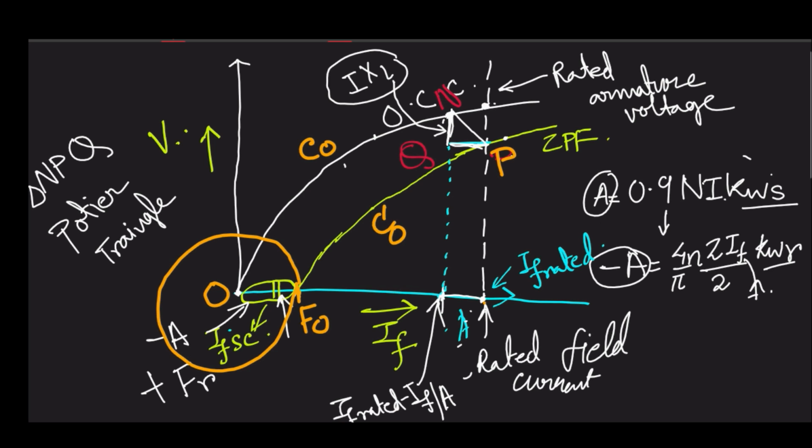Means you do not need to construct the full zero power factor characteristic curve experimentally, by stepwise variation, where you have to find a variable zero power factor load and then by varying it step by step construct the zero power factor curve.